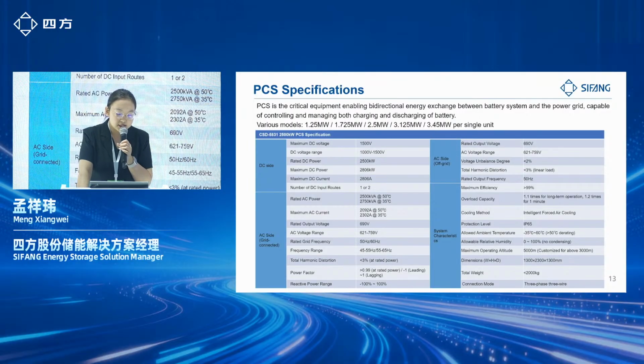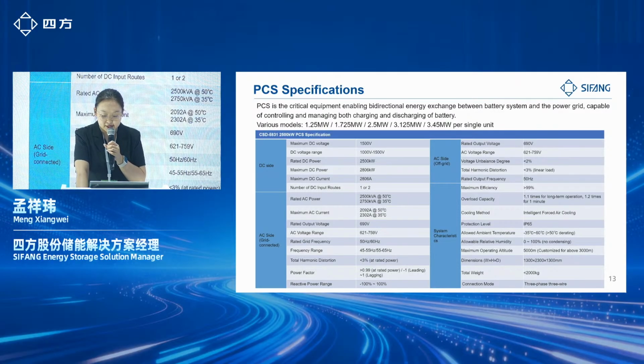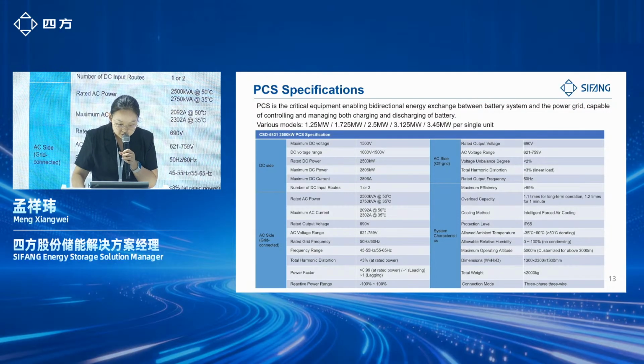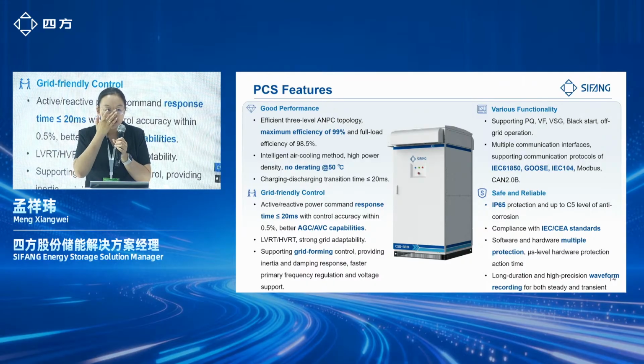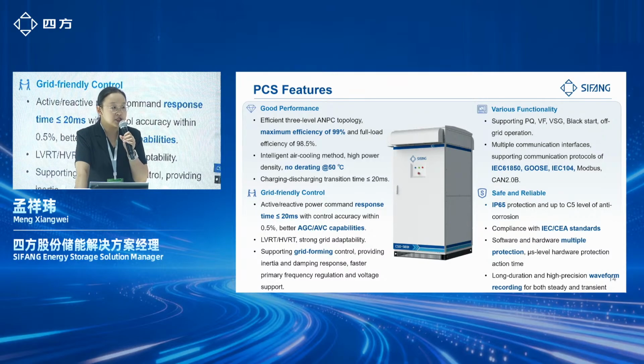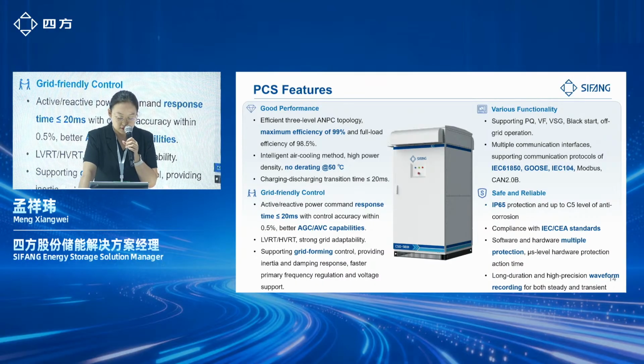As we know, the PCS is the essential equipment in the energy storage system, which enables bidirectional energy exchange between the battery system and the power grid, and is capable of control and management for both charging and discharging of the battery. Our PCS has the following advantages. First, we adopt the three-level ANPC topology, which leads to high efficiency. We have a maximum efficiency of over 99% and a full load efficiency over 98.5%.